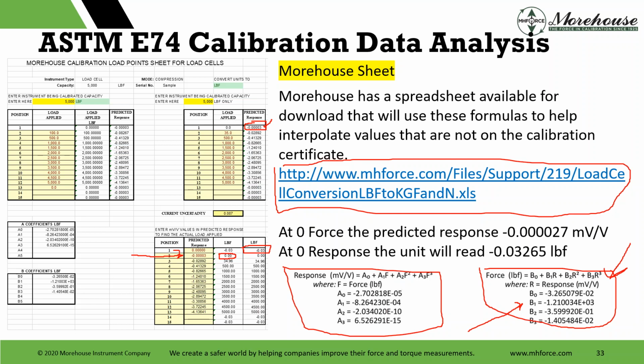These are the instructions for curve fitting. You should not be able to use this device below its first calibrated point. And hence, a lot of people get thrown that say, hey, when I zero the meter, I expect it to read 0. And my answer is always going to be, at 0 force, the predicted response is this, and at 0 response, the unit will read whatever the B0 coefficient is. So when we're using that B equation, when we put 0 through it, see, nothing is clearing out. So this is basically the B0 plus BR. R is the response.